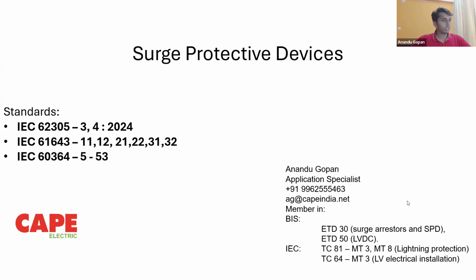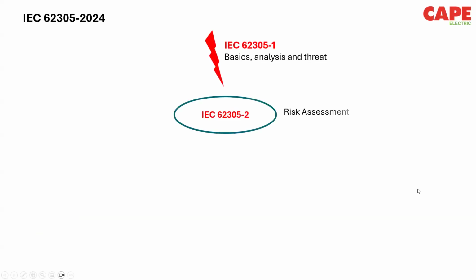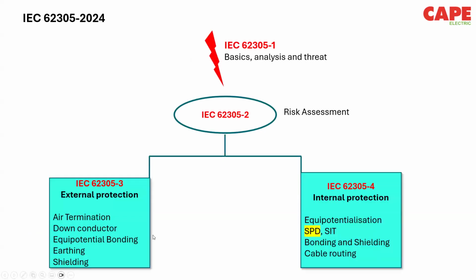Now, jumping back to our topic, let me just stop sharing my video, and then we can have better bandwidth. In IEC 62305 we have part 1, part 2, part 3, and part 4. We will be discussing majorly part 4, or some parts of part 4, and then we will be covering the 60364 standards. In part 4, SPD is a big subject because we are talking about internal protection. Internal protection means protecting all the equipment inside the building, and to achieve equipotential bonding we need SPDs. We select SPDs based on two things: one is lightning protection level, and the next is lightning protection zones. At every zone entry, we will have an SPD to further reduce the surge currents entering your building.